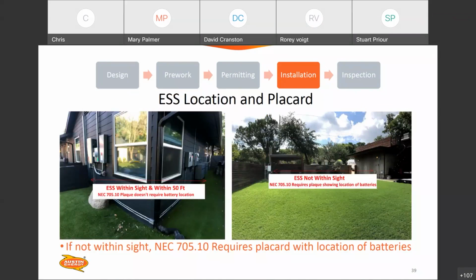When do you need a placard at the service equipment showing the location of batteries? If batteries, energy storage, or solar disconnects are within 50 feet and you can stand in one spot on site and see all of the equipment, we'll consider that within sight. If you go further than that, or if your batteries are on the other side of the house, you will need a hard, permanent, mechanically attached placard at the service showing the location of those batteries and disconnects. Please refer again to 705 - it's a gold mine for good information as far as placards go and interconnection status.